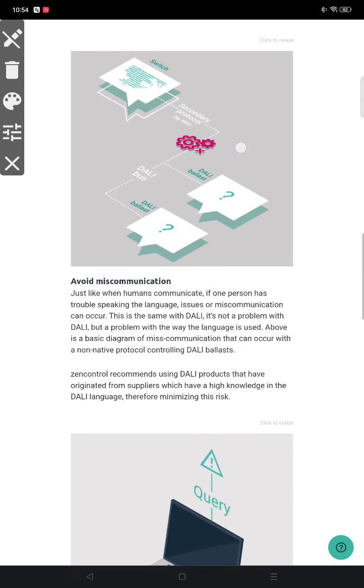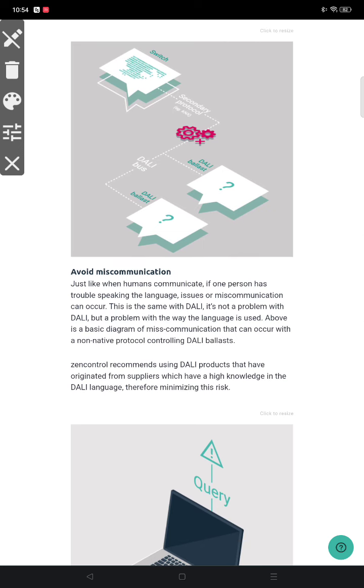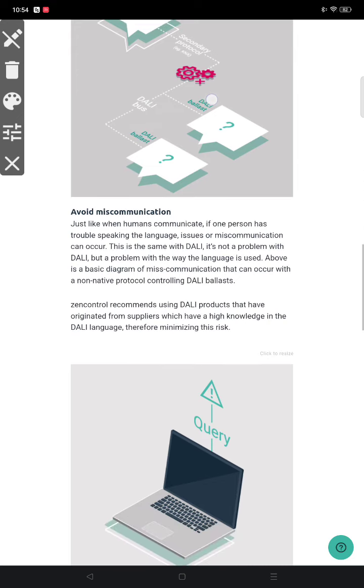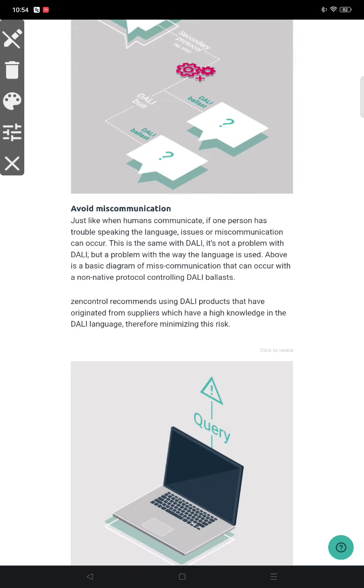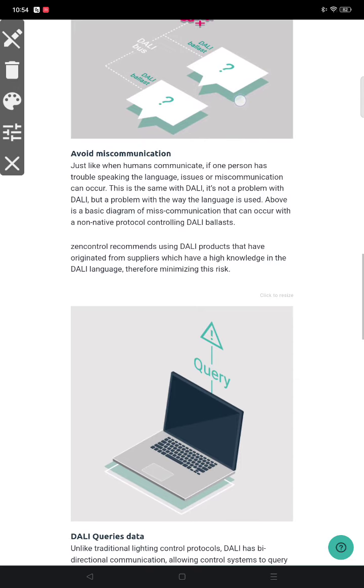Okay, avoid switching between secondary protocol, DALI ballast and DALI bus. Avoid miscommunication. Just like when humans communicate, if one person has trouble speaking the language, issues or miscommunication can occur. This is the same with DALI. It is not a problem with DALI, but a problem with the way the language is used. Above is the basic diagram of the miscommunication.